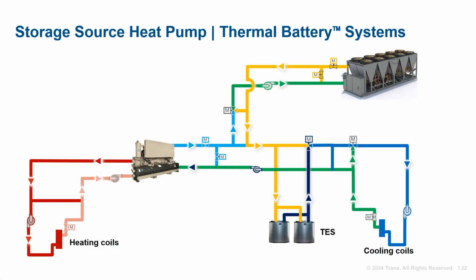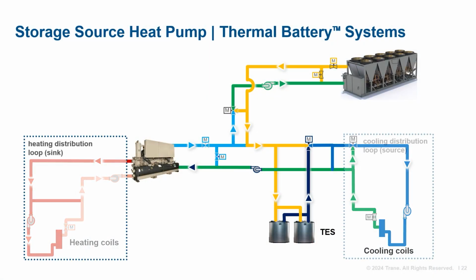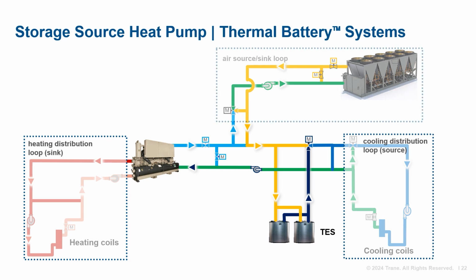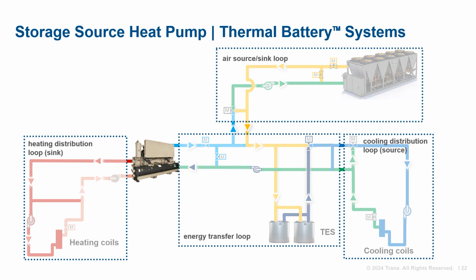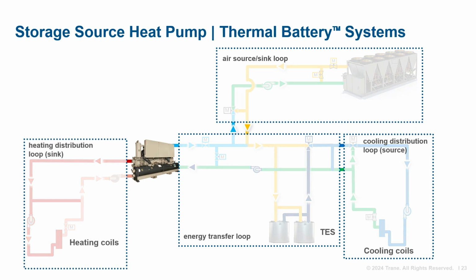Storage source heat pump systems include a heating distribution loop, a cooling distribution loop, an air source and sink loop, and an energy transfer loop containing the thermal energy storage tanks. Air-to-water heat pump units source and sink energy from outside air to or from an energy transfer loop. They're also able to provide chilled water to the distribution loop. The water-to-water heat pump, which is a chiller controlled to a heating fluid set point, provides hot water to the heating distribution loop by extracting energy from the energy transfer loop, in turn freezing the tanks.